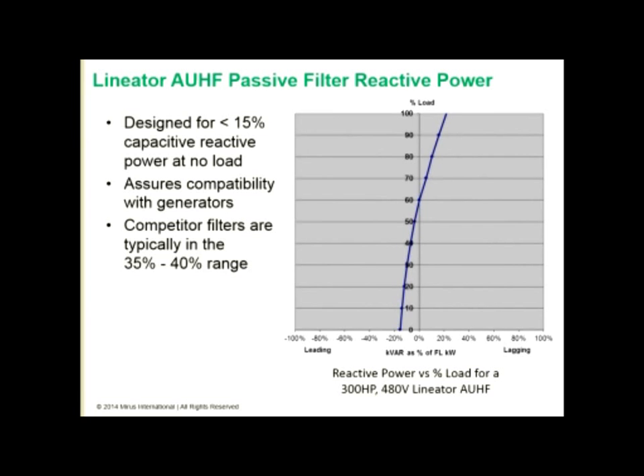So a key design parameter is that we ensure that the capacitive reactive power is never greater than 15%. This is particularly at no load, where at higher loads the filter becomes inductive, but at lower loads the filter becomes slightly capacitive. So our capacitive reactive component, you can see at no load, never exceeds 15%. Here on the x-axis, on the left side, we're showing leading reactive power as a percentage of the full load rating of the filter, and on the right side we have lagging reactive power. And although we do introduce leading reactive power at these lighter loading conditions, it never goes above 15% of the total kVAR, or total kilowatt rating.